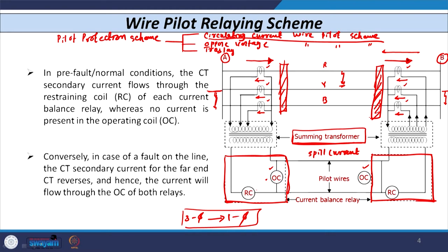If we use the opposed voltage scheme or Translay type scheme, the schematic diagram remains the same. The only difference is in the connection: the voltage across the relay coil is in opposition under normal conditions. The relay available in the opposed voltage scheme is a voltage-based relay, not a current-based relay. Under normal conditions, opposite voltage is available, so the relay stays stable, and in case of internal fault, it operates. The same logic applies to the Translay scheme.